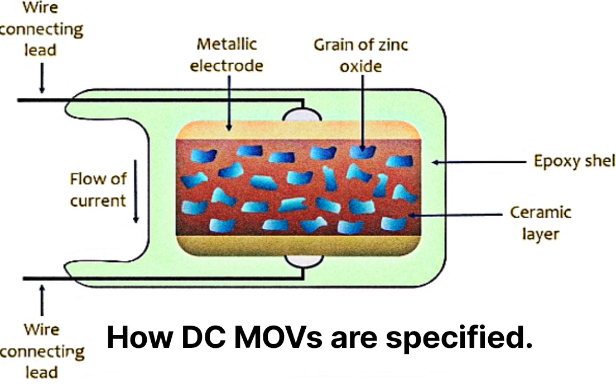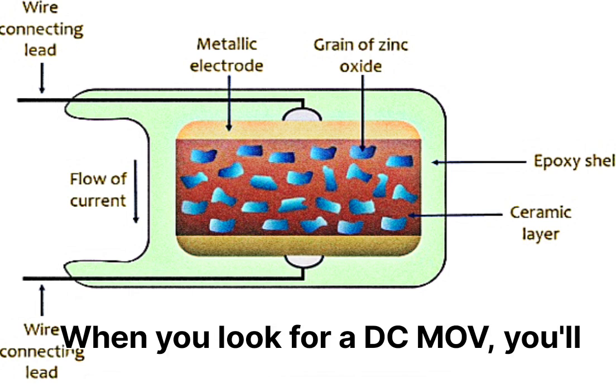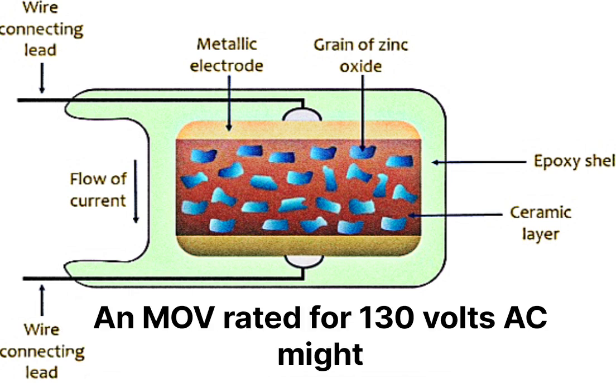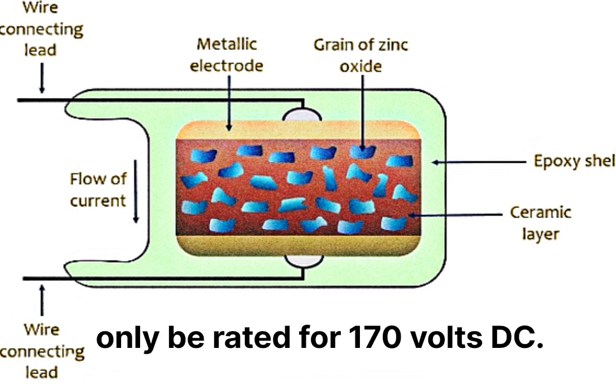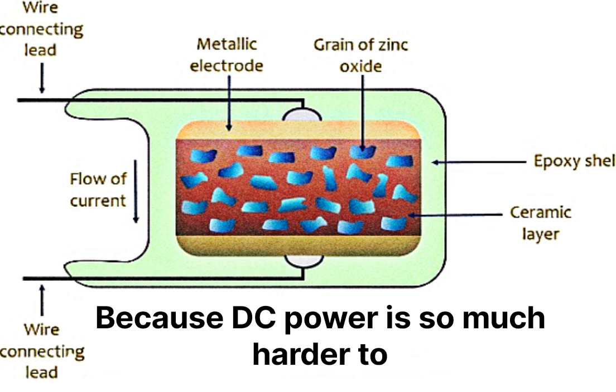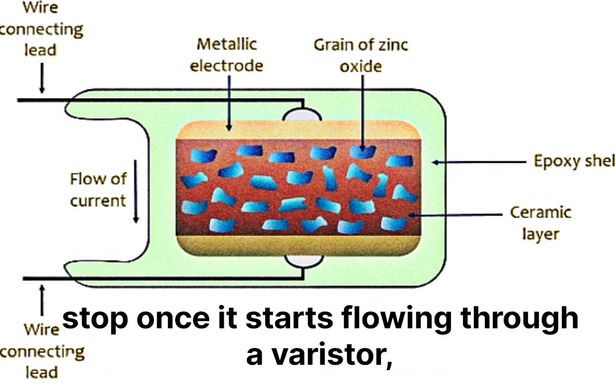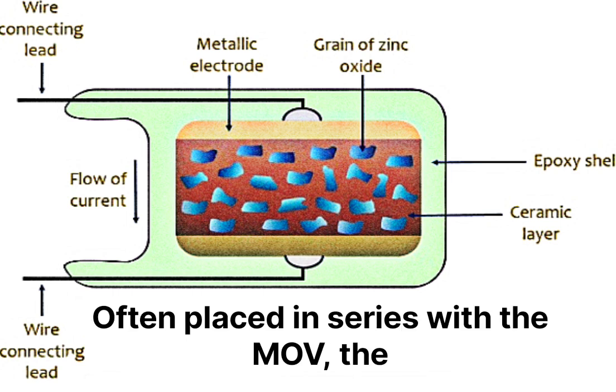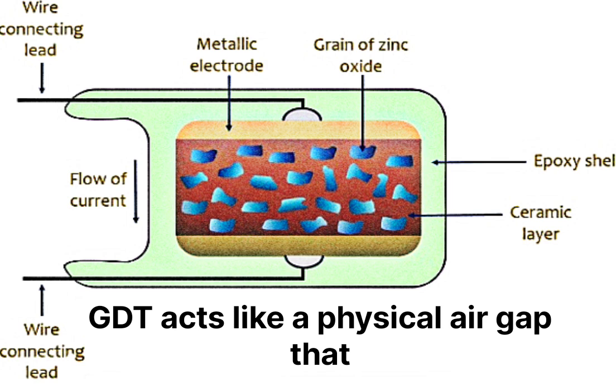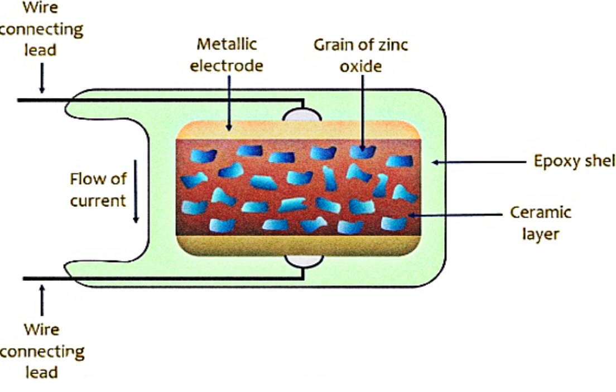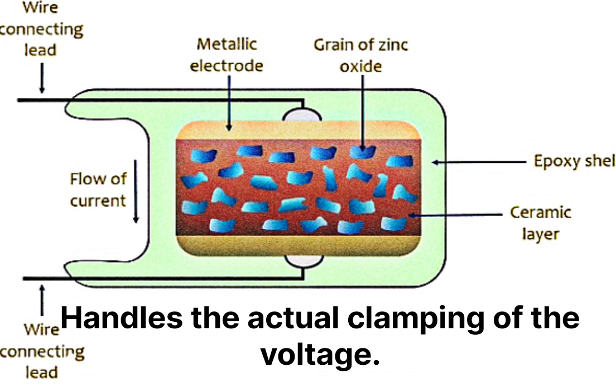How DC MOVs are specified. When you look for a DC MOV, you'll notice the ratings are different. An MOV rated for 130 volts AC might only be rated for 170 volts DC. The DC hybrid approach. Because DC power is so much harder to stop once it starts flowing through a varistor, engineers often don't use the MOV alone. They use a hybrid protection circuit. One, a gas discharge tube, GDT, often placed in series with the MOV. The GDT acts like a physical air gap that blocks all leakage current. Two, the MOV handles the actual clamping of the voltage.